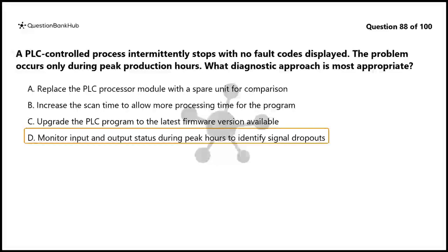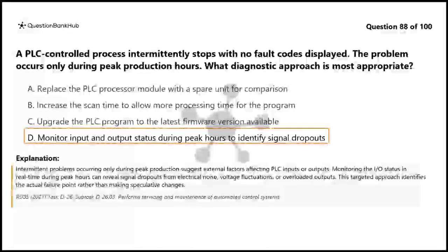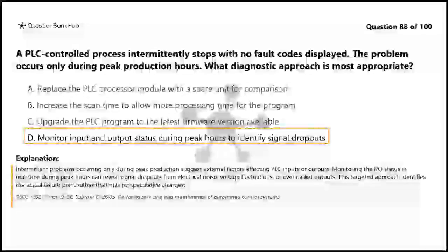The correct answer is D. Monitor input and output status during peak hours to identify signal dropouts. Intermittent problems occurring only during peak production suggest external factors affecting PLC inputs or outputs. Monitoring the I/O status in real time during peak hours can reveal signal dropouts from electrical noise, voltage fluctuations, or overloaded outputs. This targeted approach identifies the actual failure point rather than making speculative changes.